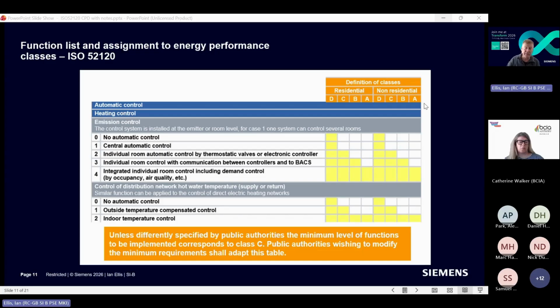Now, the one thing to say with all of this, as you're going up the classes from D to A, and again, I know you're all in the control industry, so I'm not here to insult anyone's intelligence, is that I'm adding levels of control. I'm probably adding additional control equipment. If I add an occupancy sensor into a room that hasn't had one, yes, I'm adding another device. Let's say I make that a CO2 sensor rather than just an on-off occupancy detector, I'm adding probably a bit more cost in. So there's more initial capital cost to go from a Class D system to an A system, or if you're doing the design, you need more controls in a Class A than a Class D.